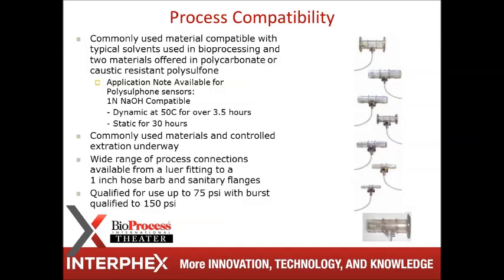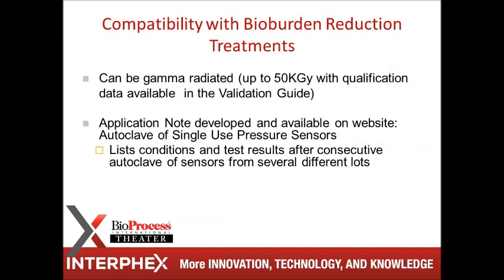And we also have done testing up to as high as we could go, which is 150, with no change in performance or detrimental effects. Any exposure beyond that would pretty much cause other components to fail, such as tubing and whatnot, so we felt 150 was a good range. We've demonstrated with this product no change after exposure to gamma, and we have application notes on autoclaving, which describe conditions which don't impact their performance.